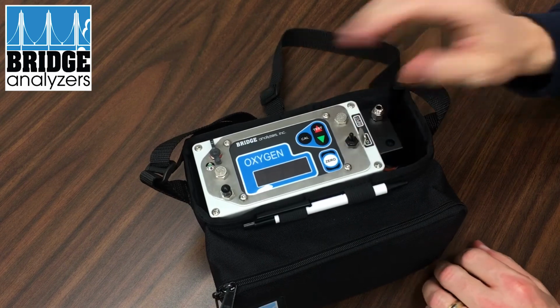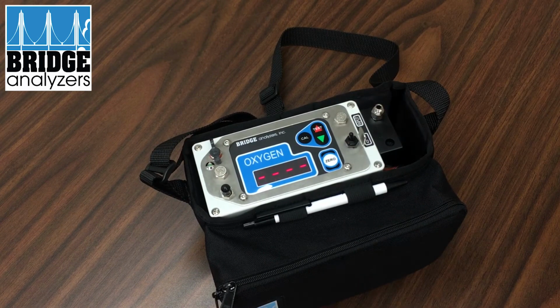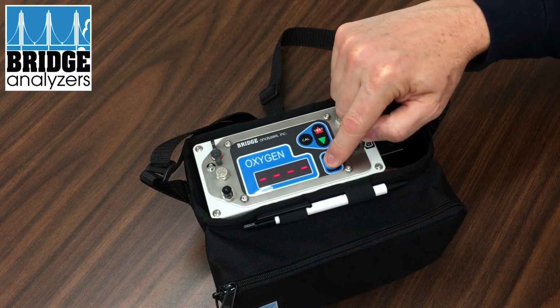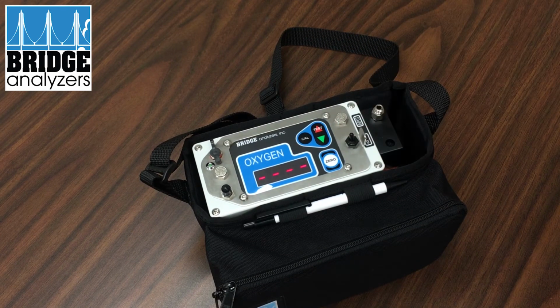Now you can put it in the case, turn it on, and now you're back to standard procedure where you'll zero. And then after it zeros, it will display a reading of 20.9, which is the reading for air, and that process is a calibration of the new sensor. So no other need to do any other calibration. It should just auto-calibrate in this way. So we can just wait and you'll see the 20.9 show up to indicate that we have a good reading. So there's our 20.9 and we're off and running.